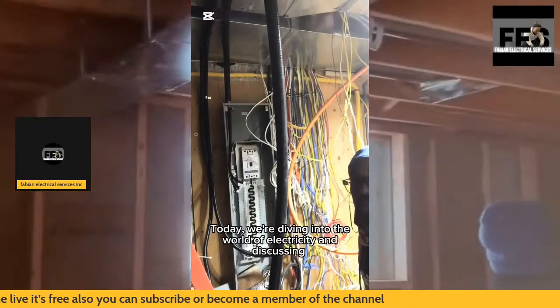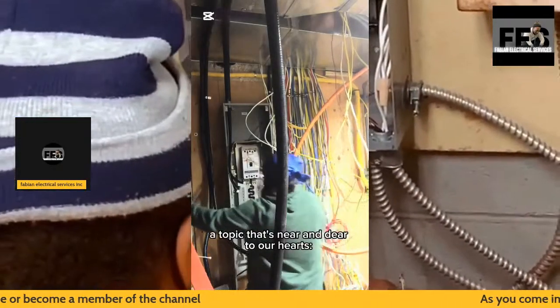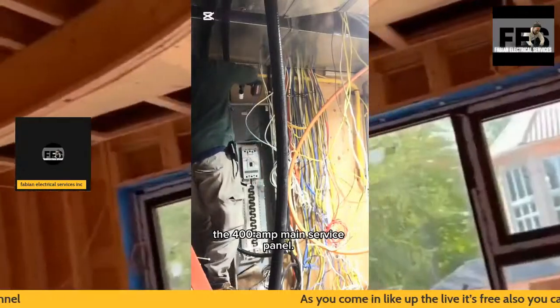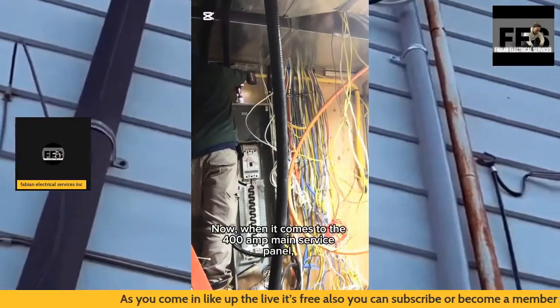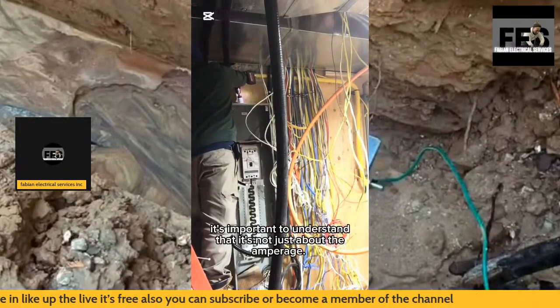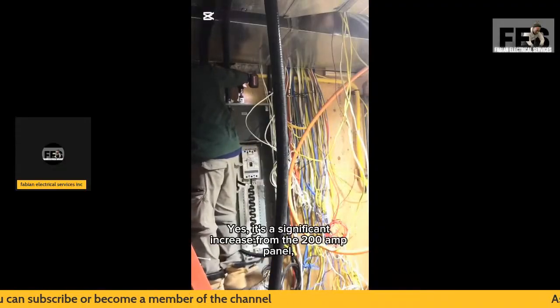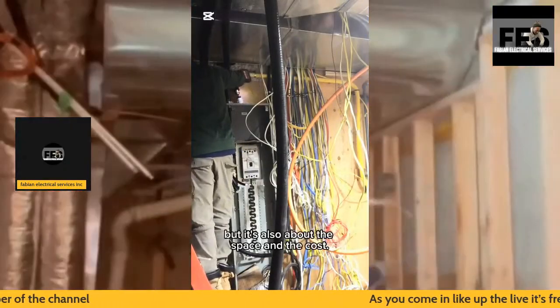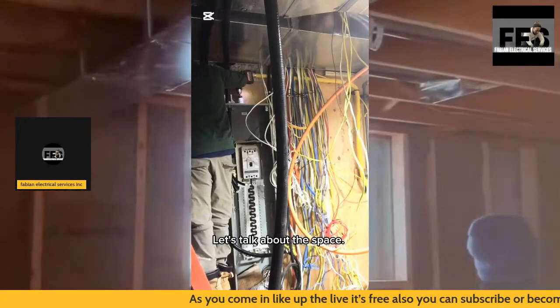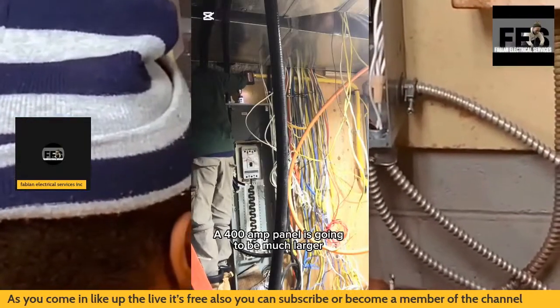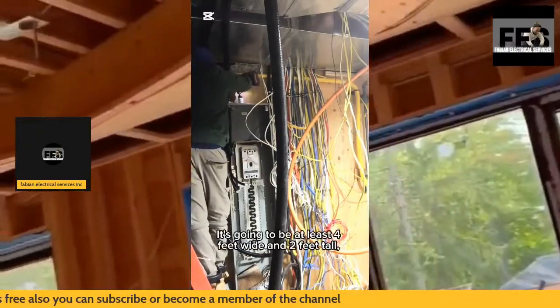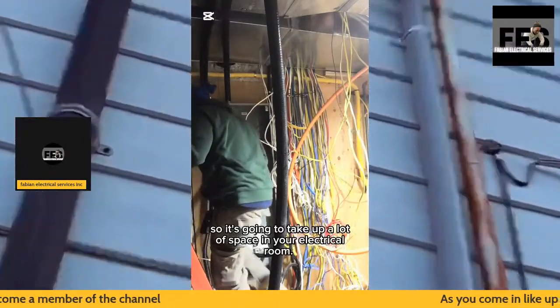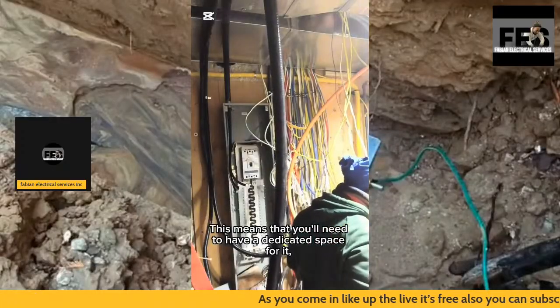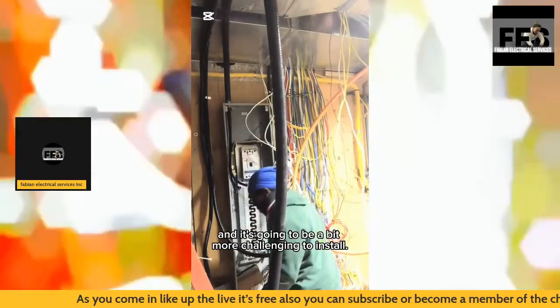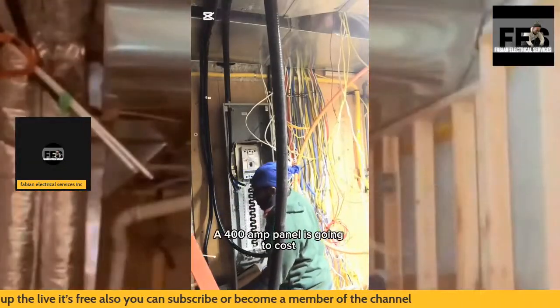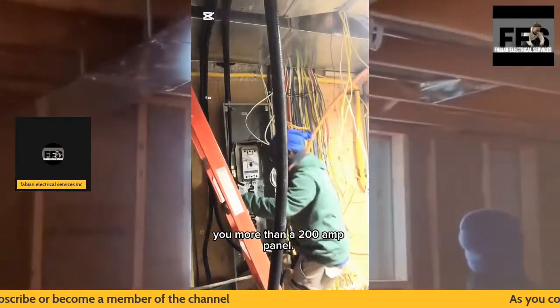Thank you guys for tuning in to today's video. What we have here is a 400 amp electrical panel, and the installation involves the main feeders coming in, which is 400 amp for the 400 amp service. These are 250 kcmil parallel feed cables that I'm running, and the cables are the same length — with parallel runs, you have to make sure the lengths are all the same. I'm going to the top of the 400 amp distribution service, that's where I'll land my wires from the top. As you can see, I have one set of cables landed.